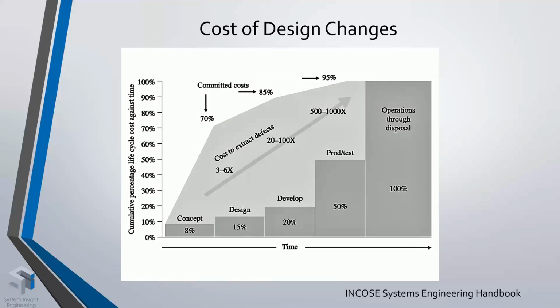On the other side, we want to know more about our devices earlier in the process. From the Systems Engineering Handbook, we've got this example here, where even at the concept phase, where we've really committed through 8% of the design itself, a lot of the decisions that are made are upwards of 70% of what's eventually going to go into the device. So decisions are being made at the concept phase that are really going to drive about 70% of what that device is going to look like, even though you've kind of tested more along the lines of 8% of that performance. And the further you get through that system, the more those costs go up. So from concept to production, you can have a 1,000-fold increase in cost to fix some of those defects. As anyone that's ever had to go back and retool production tooling knows, those are obviously things that you want to avoid. It's a painful process, of course.